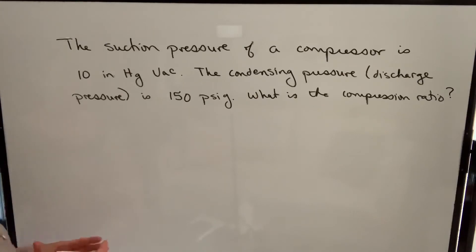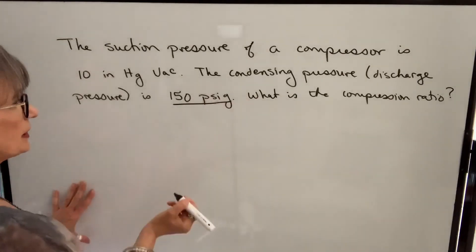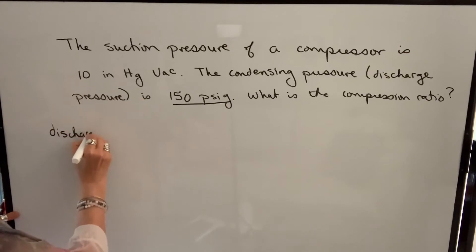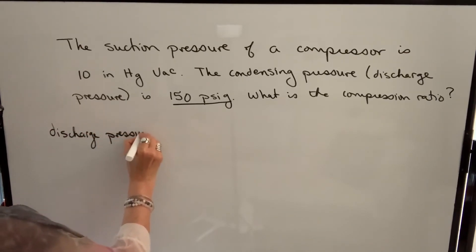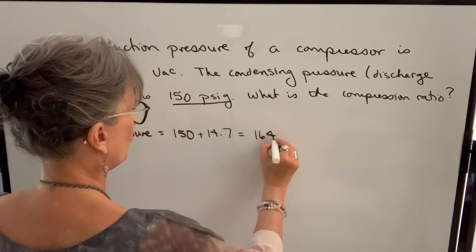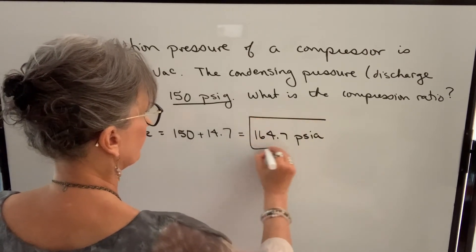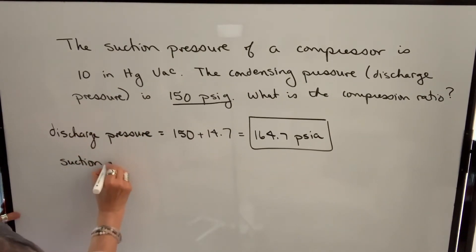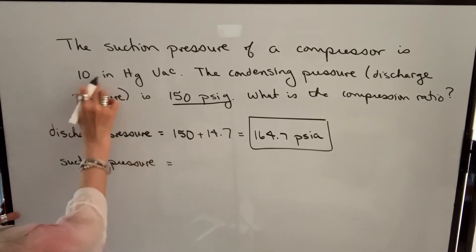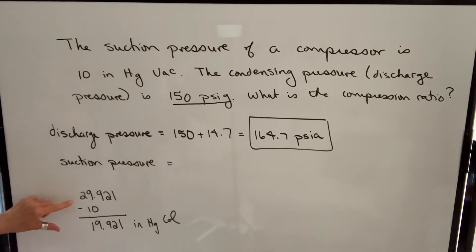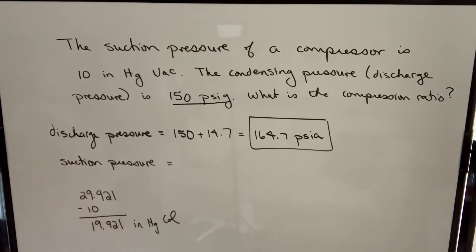We have two pressure units to convert. For the discharge pressure of 150 PSIG, we add 14.7 to get 164.7 PSIA. For the suction pressure of 10 inches mercury vacuum, we first convert to inches mercury column by taking 29.921 minus 10, which gives 19.921 inches mercury column.